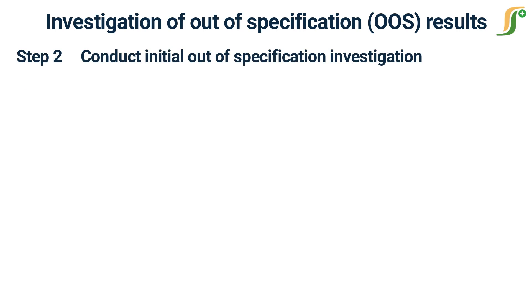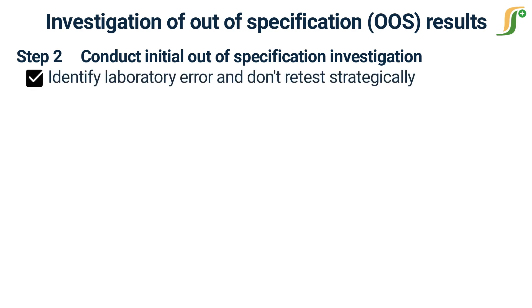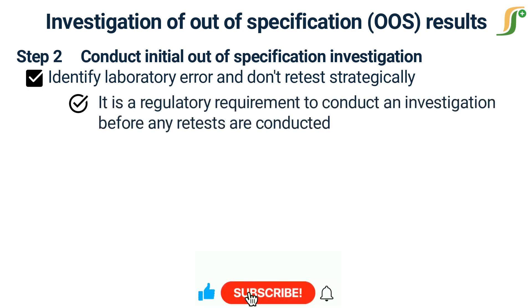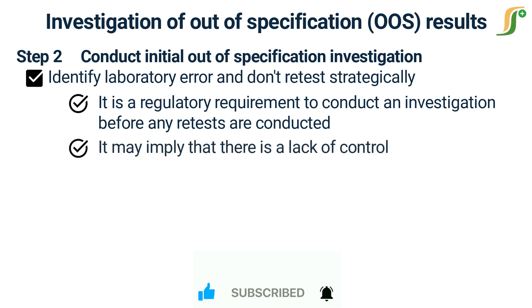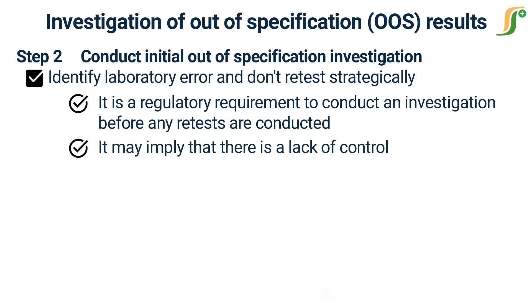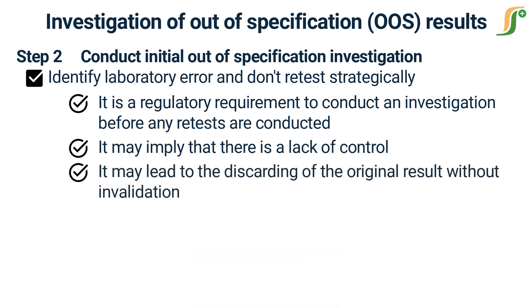The exact cause of an out-of-specification event can be difficult to determine with certainty, and it is unrealistic to expect that analyst errors will always be documented. Simply retesting as a strategy raises three problems: it is a regulatory requirement to conduct an investigation before any retests are conducted; it may imply a lack of control; and the laboratory may not address the causes of possible failures, allowing those conditions to recur on the retest. It may also lead to the discarding of the original result without invalidation. Therefore, it is essential that a laboratory predetermines its course of action in the event of an OOS.